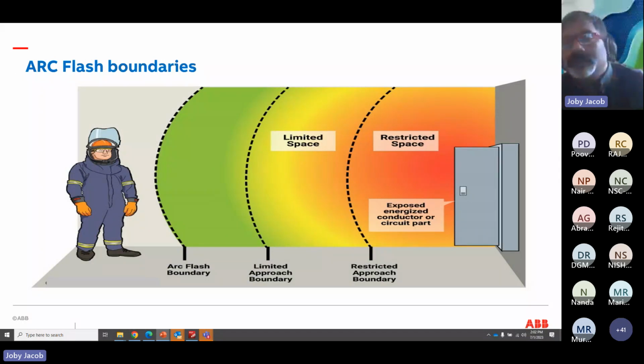You see on the right hand side, if you are too close, where we are in front of the panel, we call it exposed energized conductor. This is the restricted approach boundary. In this place, you are vulnerable not only to arc flash but also to electrical shock. So a technician or an electrician in that workspace should be adequately protected. When I'm talking about protected, he is in front of a live panel, which has the potential for some sort of failures. Then he is vulnerable to all kinds of electrical shock as well as arc flash. So that's the restricted approach space, basically.